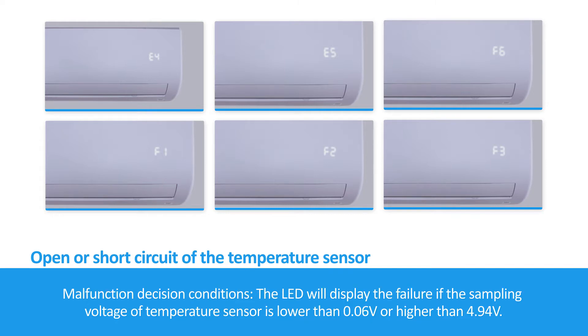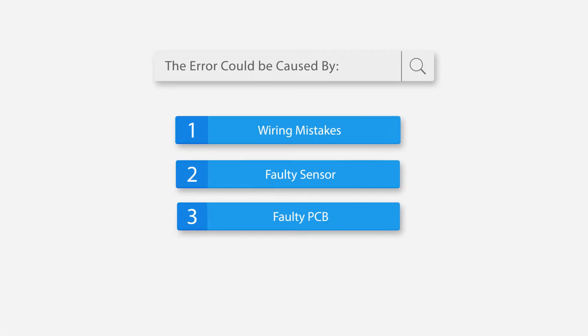Malfunction decision conditions: The LED will display the failure if the sampling voltage of the temperature sensor is lower than 0.06 volts or higher than 4.94 volts. The error could be caused by: 1. Wiring mistake, 2. Faulty sensor, 3. Faulty PCB.